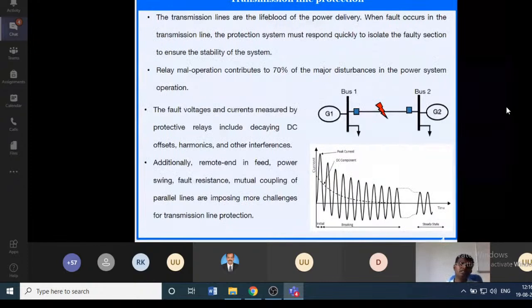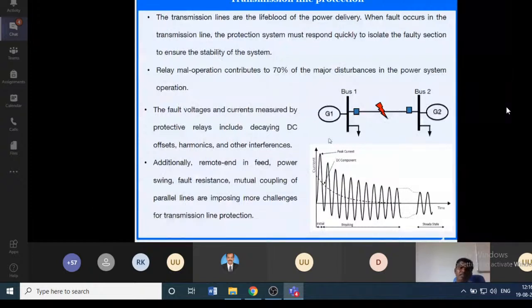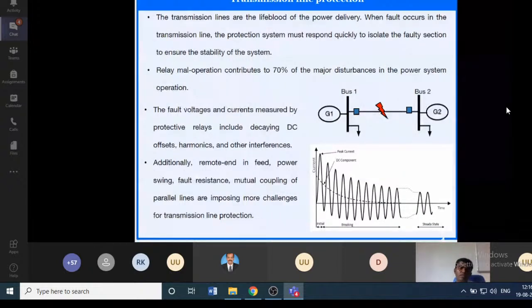The first application is transmission line protection. In the introduction part, we discussed the role of the protection system in maintaining the stability of the system. The system may have subtransient and transient periods. In the subtransient period, there is a peaky non-sinusoidal waveform, but the relay has to estimate the fundamental harmonics and detect the fault, right?